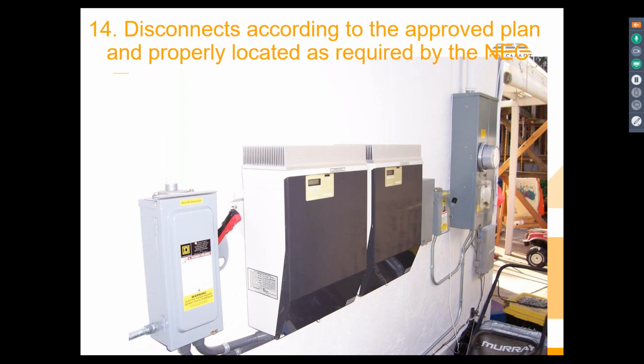But the reality is, if you really want to improve safety of the firefighters, you've got to do it in a comprehensive manner. That's because they were going to put this in the fire code in 2012 - a rooftop disconnect required for every PV system. So I talked to the guy who was putting the requirement in, and I wrote him a 4-page document on why you cannot make that a requirement, because it's not going to do anything of what you think it's going to do.